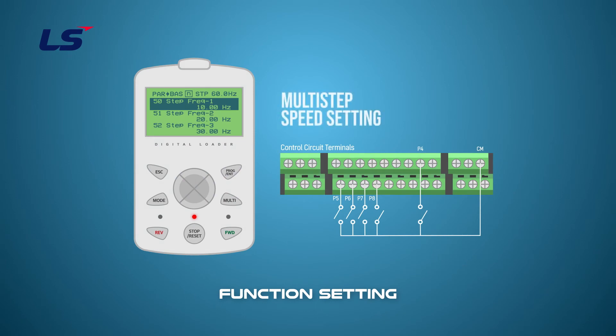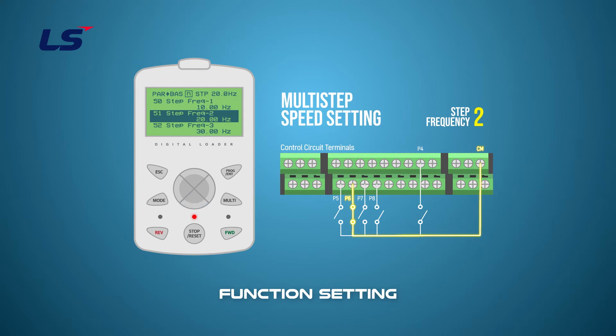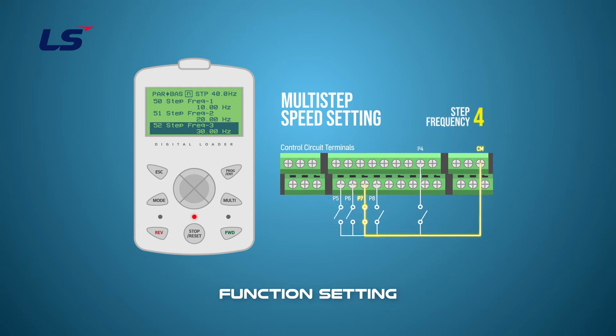Terminal P5 means step 1, and the frequency setting for step 1 is set at BAS50, step frequency 1. P6 stands for step 2, and the frequency setting for step 2 is set to BAS51, step frequency 2. If terminals P5 and P6 enter simultaneously, this means step 3, and the frequency setting for step 3 is set to BAS52, step frequency 3. Terminal P7 stands for step 4, and the frequency setting for step 4 is set to BAS53, step frequency 4. This series of combinations allows you to set the speed of each step up to BAS56, step frequency 7.